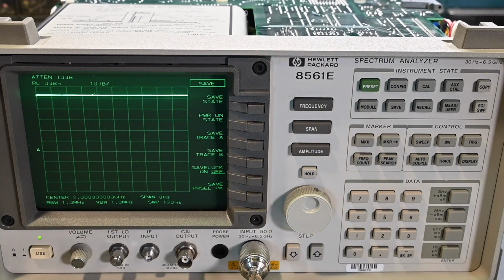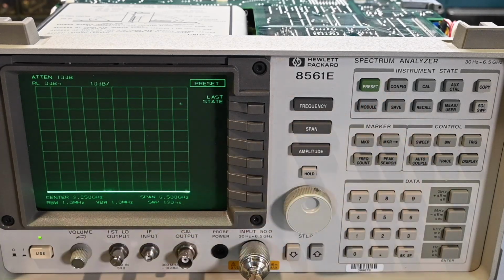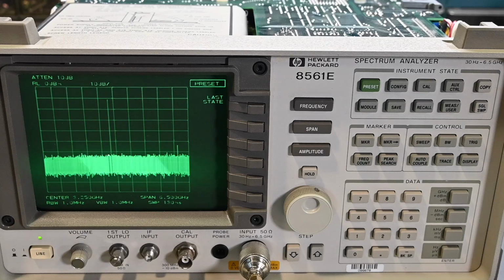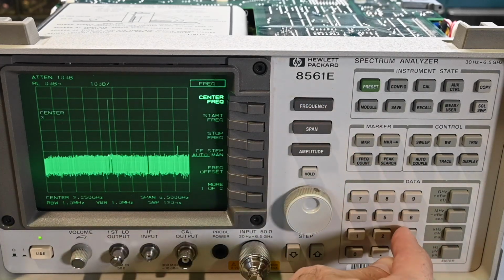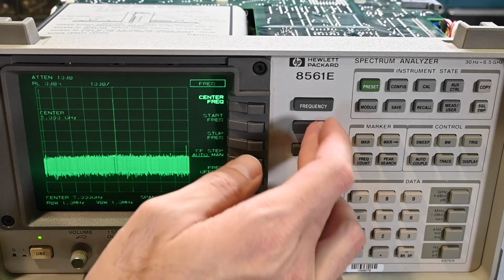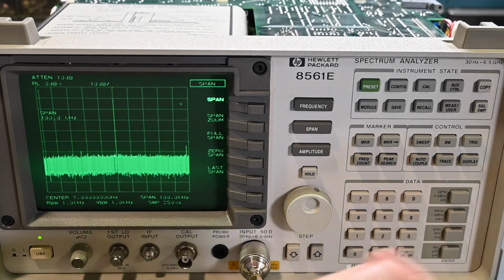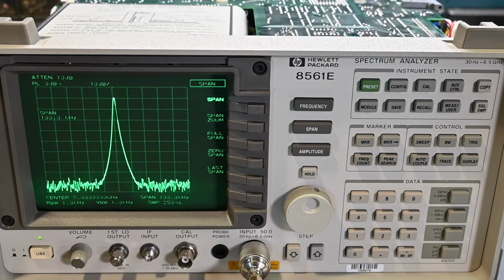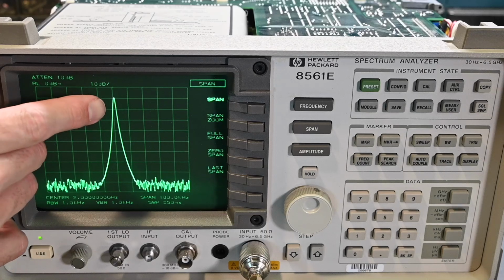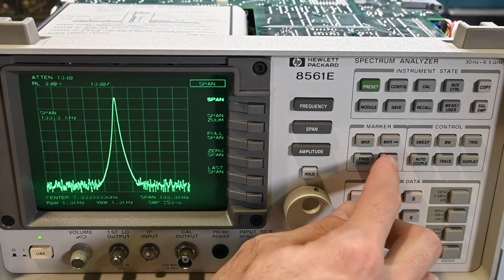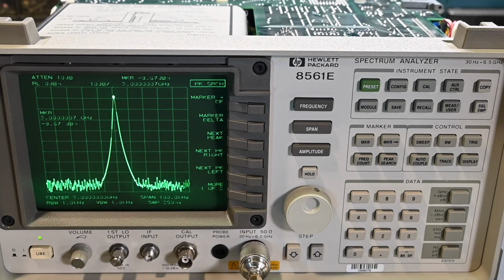Let's take a couple measurements and see how the spectrum analyzer looks. So let's do this here. Do a preset. So the signal generator is at 3 gigahertz, so we'll go frequency 3 gigahertz and span 100 kilohertz. Hey, look at that. Not too bad. That looks really good. So minus 10 dBm, that's second graticule down. So let's do peak search. And what do we see? So the marker is at minus 9.67 dBm. Really good. I don't see any issues with that. That's so close. Very, very close to that minus 10 dBm level. So calibration successful. It looks like it's working very well.